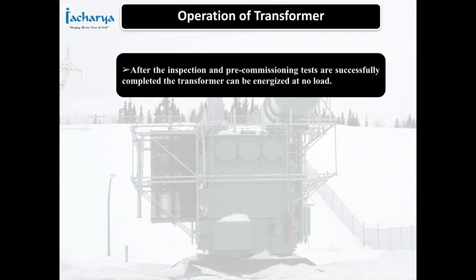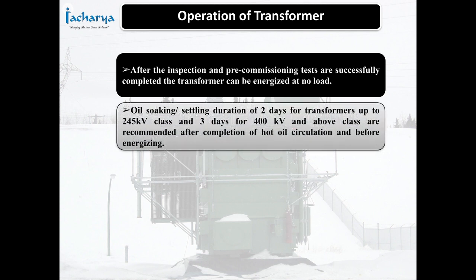Operation and maintenance of transformers. After the inspection and pre-commissioning tests are successfully completed, the transformer can be energized at no load. Oil soaking or settling duration of 2 days for transformers up to 245 kV class and 3 days for 400 kV and above class are recommended after completion of hot oil circulation and before energizing.